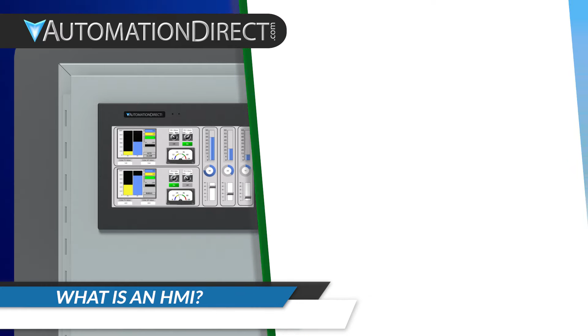HMI stands for Human-Machine Interface. It's exactly what it sounds like, the connection point between a person and a system. An HMI typically lives on the panel and connects directly to a PLC using a controller's protocol. It shows key information like system status, alarms, and maybe some trends. It also lets operators send commands through buttons or touchscreen elements. But the HMI isn't directly controlling the system, it's just relaying information to and from the controller. Commands sent are typically no more than flipping a bit. It's the PLC who holds the logic and executes the process.